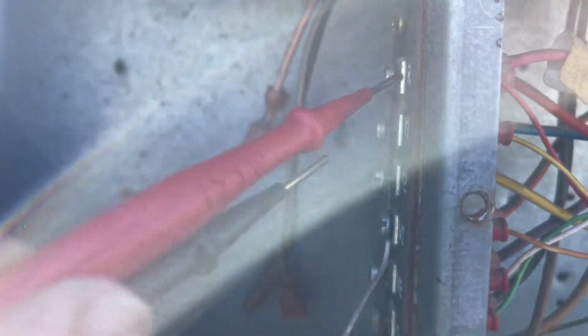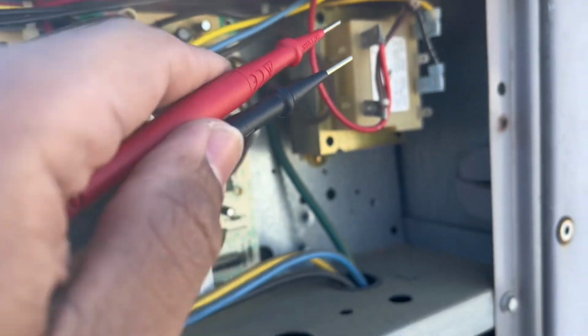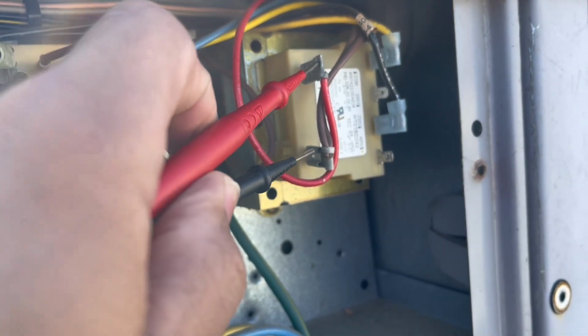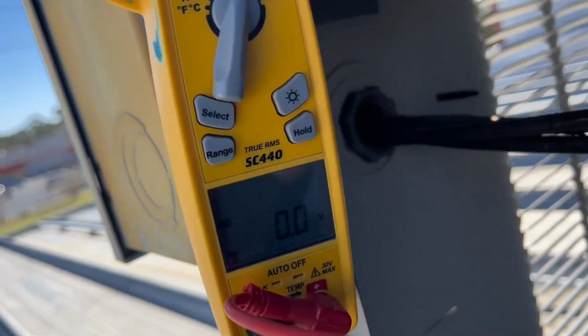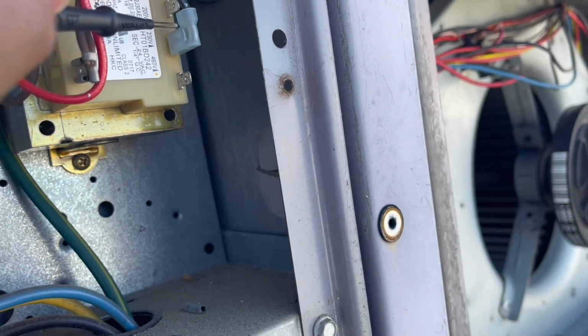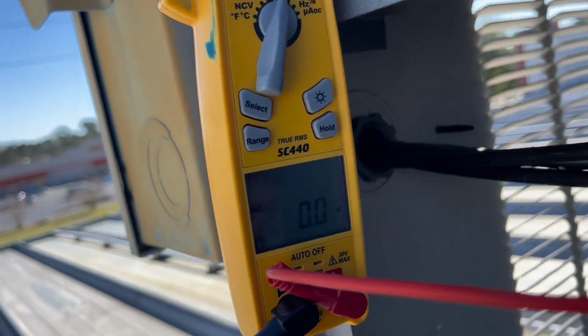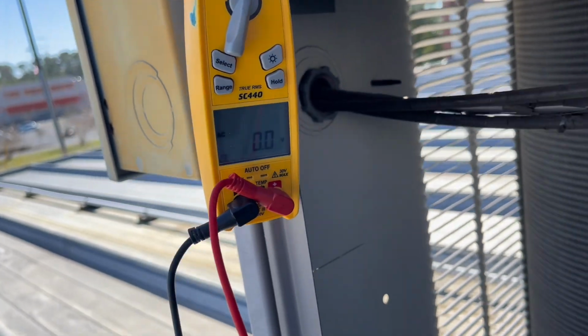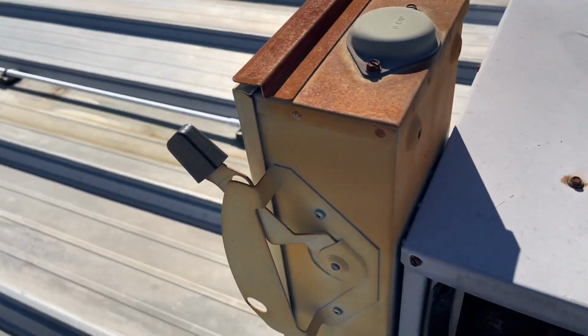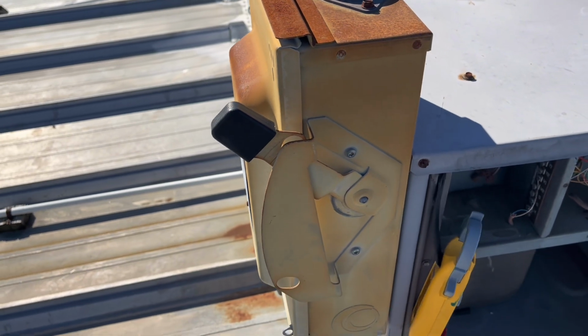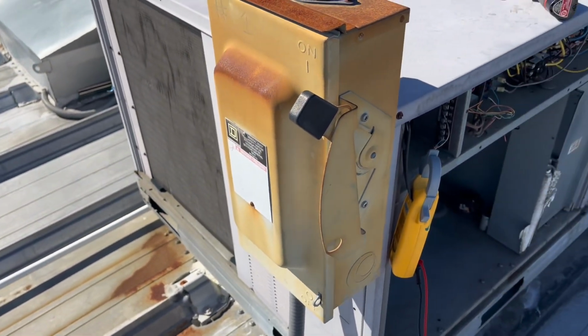Alright, so we're about to check the voltage between the thermostat and the transformer, and we're going to start here checking the connection between red and common, and we can check in our meter and confirm that we are not receiving power. The next step is going to be to check the transformer, and we're going to start on the 24 volt side, and after we confirm with our meter that it is 0, we're going to do a last thing, which is checking the 230 volts that are supposed to come into the transformer. And when we check our meter, it is 0 as well. So that means that we are not receiving power from the disconnect. So our next step is going to be to open this box right here, making sure it is wired properly and whether we have power or not. Let's check and see what's going on.